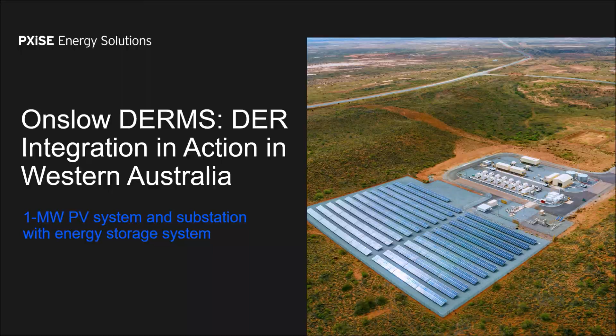Horizon Power was one of the first companies to adopt, or mandate, the use of 2030.5 in this project. This means that from the central server located in Perth, the location of the master DERMS system, it dispatches commands every 5 minutes to nearly 270 controllable DER devices located 1,400 kilometers away from the central server.